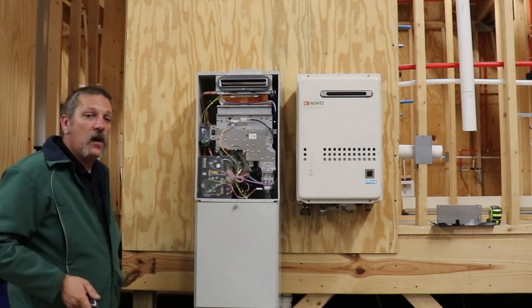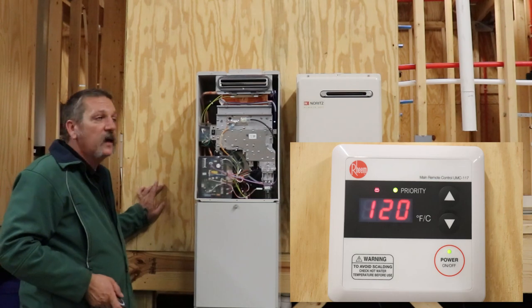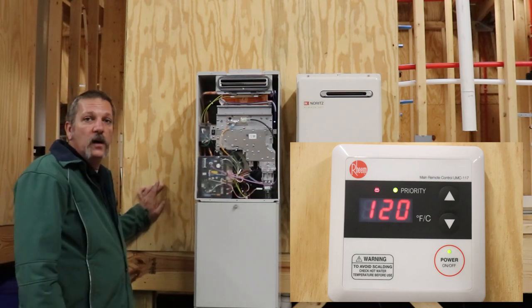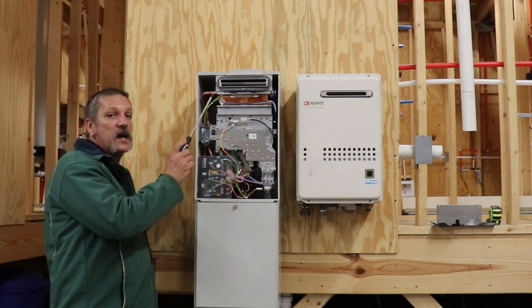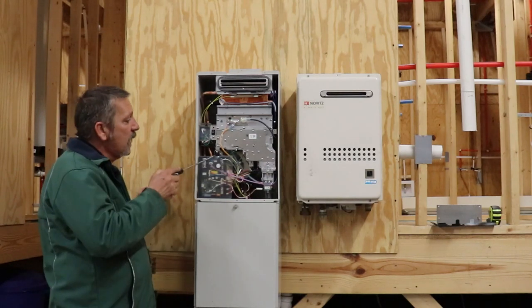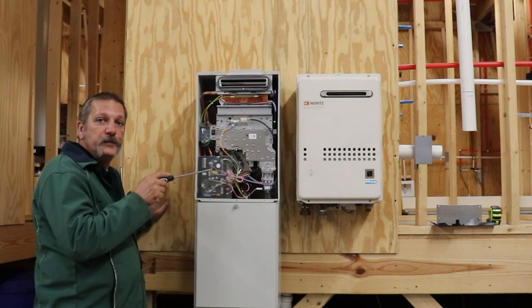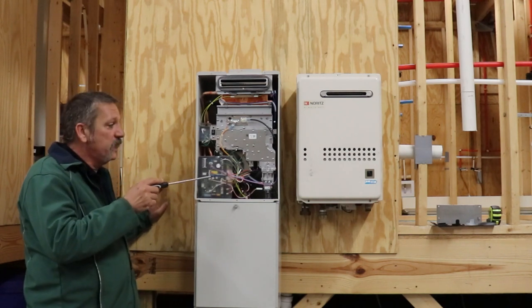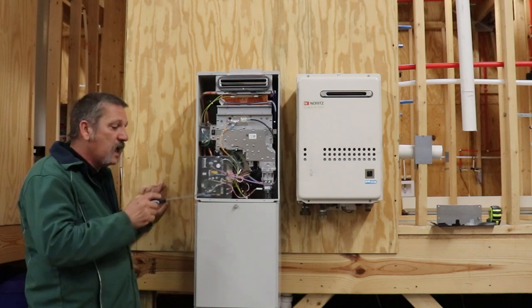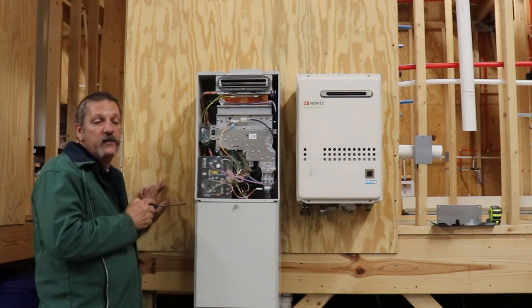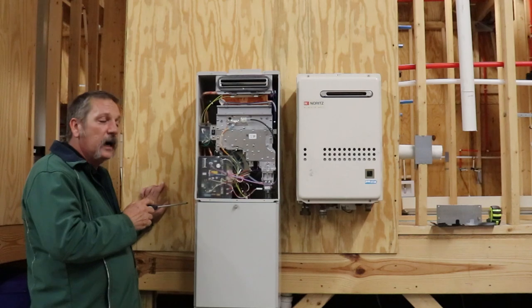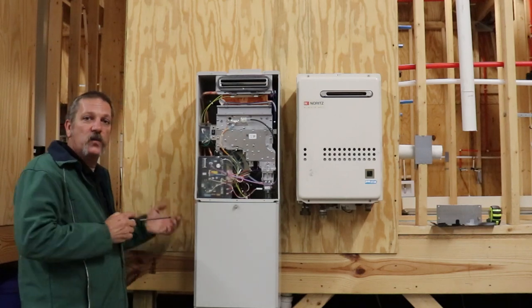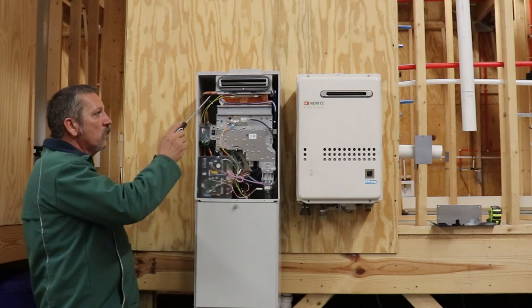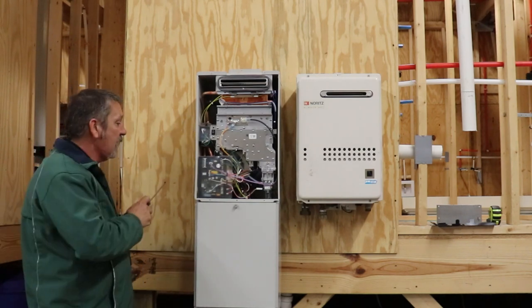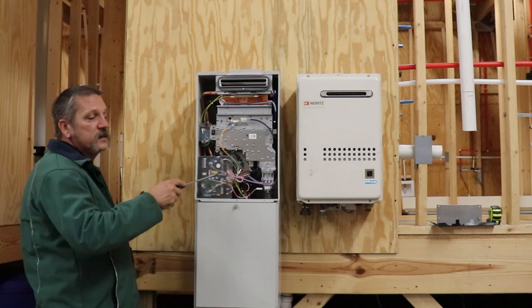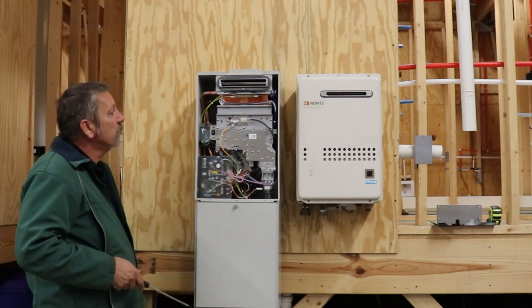Now, a lot of people think that, oh, I got my controller over here set at 120, that's gonna make 120 degree water. No, actually that's running at a lot higher temperatures than 120. It's got another little pipe down here that lets cold water come back into a bypass. It mixes the water back together to get that desired 120 or whatever you've got it set at, 130, 140 water temperature right here at the base where it's actually coming out the water heater. So this water, when it leaves that, is actually gonna be hotter than that desired temperature. And it's gonna mix a little cold back with it to temper it down.